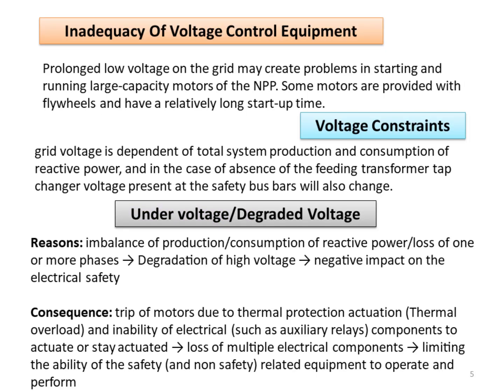Prolonged low voltage complicates the startup and operation of large NPP motors, some of which have flywheels and extended start times. Voltage stability depends on reactive power balance. Without proper tap changers, safety bus voltages can fluctuate. Undervoltage can trigger thermal protection in motors, cause relay malfunctions, and degrade safety system performance.